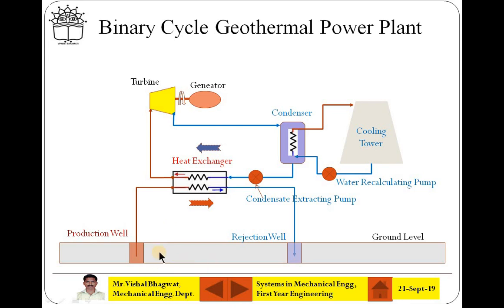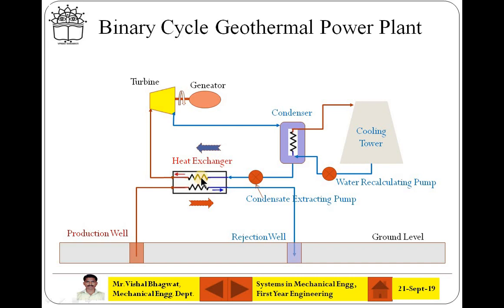In the earth crust or on the surface, some drills are made. One will be called as a production well and another drill may be called as a rejection well. From the production well, the source of heat can be obtained. As we are discussing about binary cycle, from the production well, the brine solution will be obtained which will be having very high temperature, up to 100 degree Celsius or up to 200 degree Celsius. That brine solution means salt solution is taken to a heat exchanger where it is exchanging heat to some of the organic liquids.